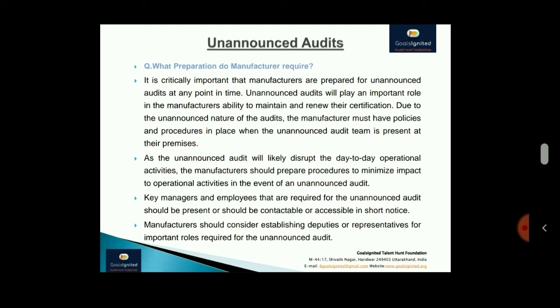As the unannounced audit will likely disrupt day-to-day operational activities, the manufacturer should prepare procedures to minimize the impact on operational activities in the event of an unannounced audit. The key managers and employees required for the audit should be present or contactable and accessible at short notice. The manufacturer should consider establishing deputies or representatives for the important roles required, so that it does not happen that all the senior and key persons are absent. A second person and a responsible person should always be present. You cannot request the auditors to come another day because you are not able to face the audit. You should always be ready to face the audit, and all the senior and key persons should be present in the plant.